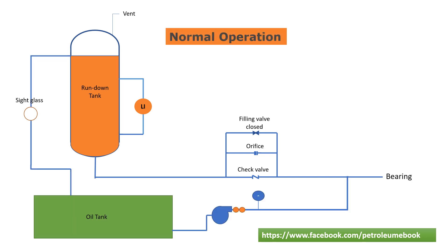During normal operation of the main equipment, the main lube oil pump keeps the lube oil supply header pressurized and maintains lube oil flow to the bearings. The run-down tank filling valve is closed and lube oil flow to the run-down tank is blocked by the check valve. This small leakage flow through the orifice plate maintains a continuous lube oil recirculation back to the lube oil reservoir through the overflow line.